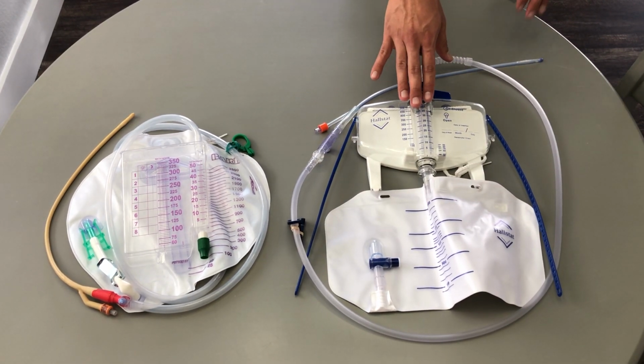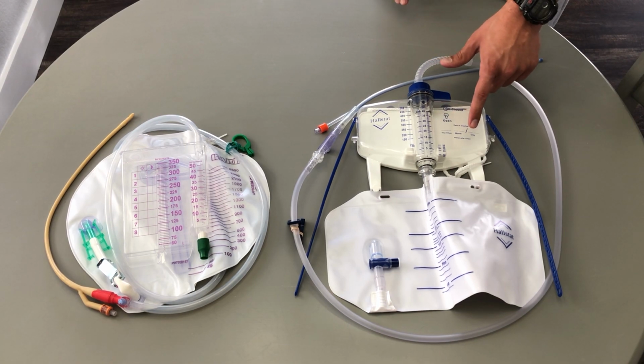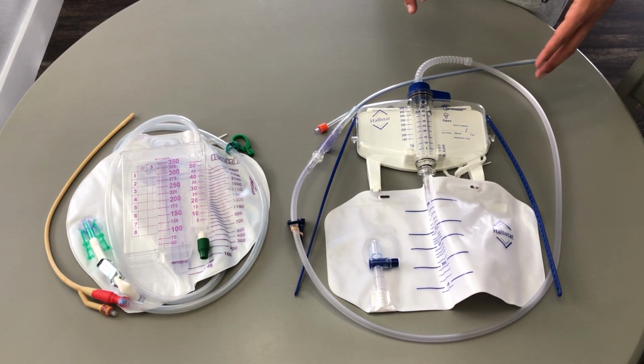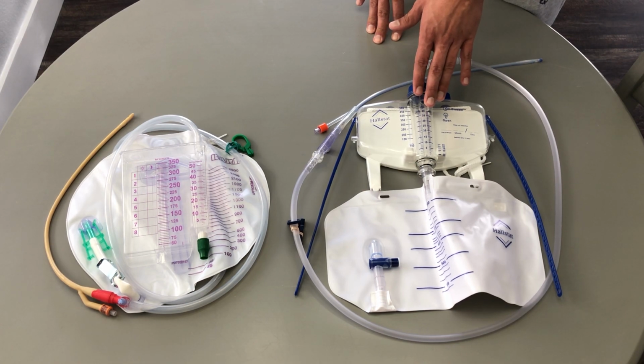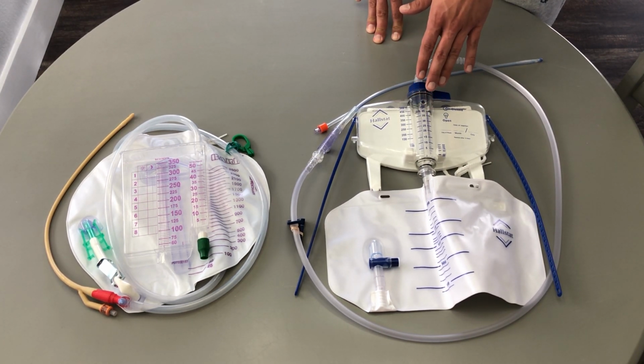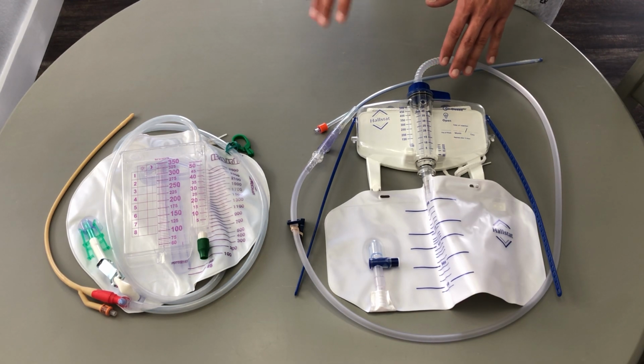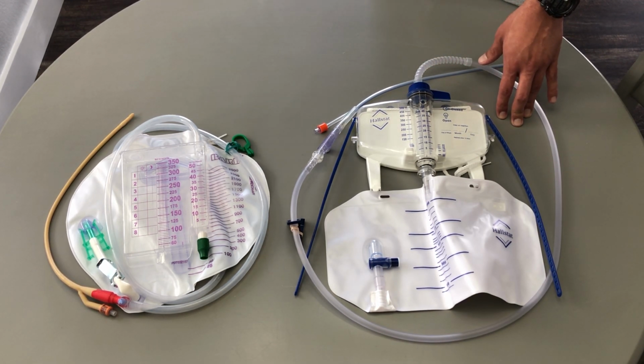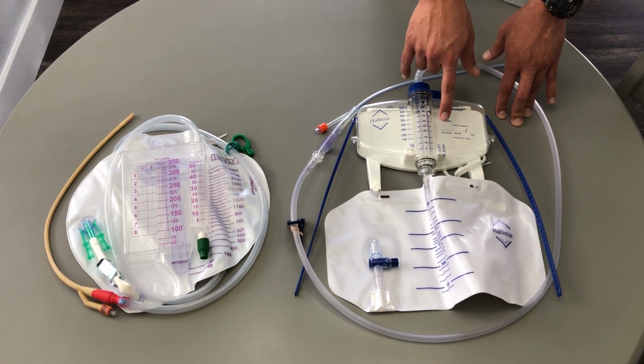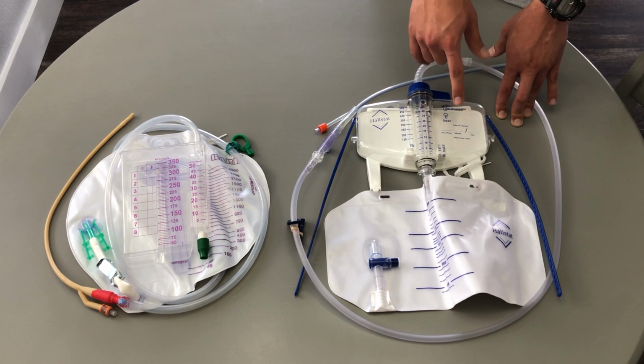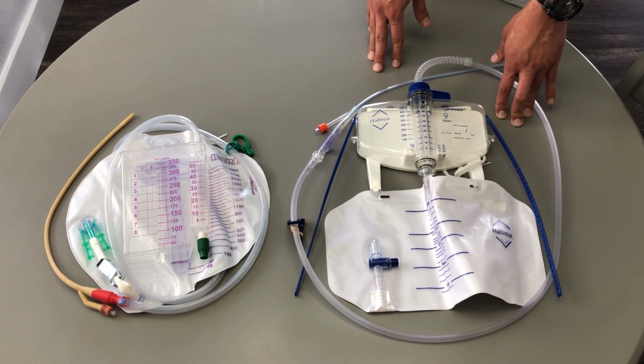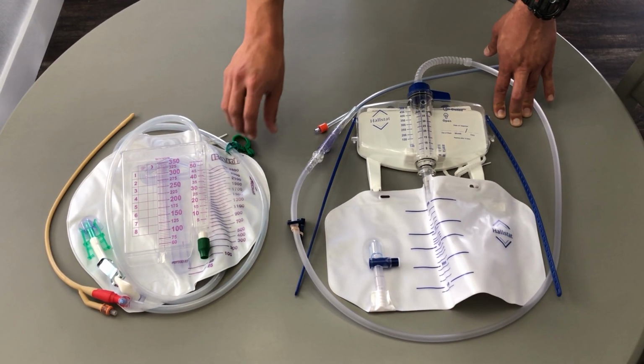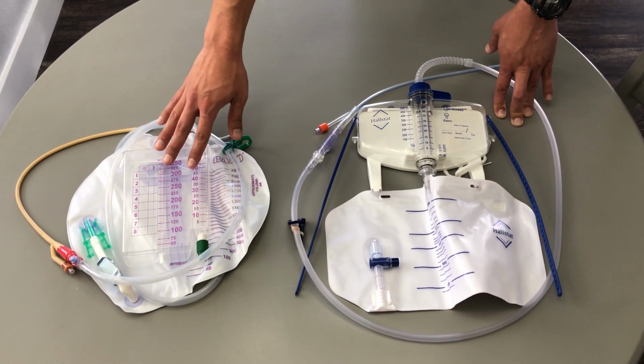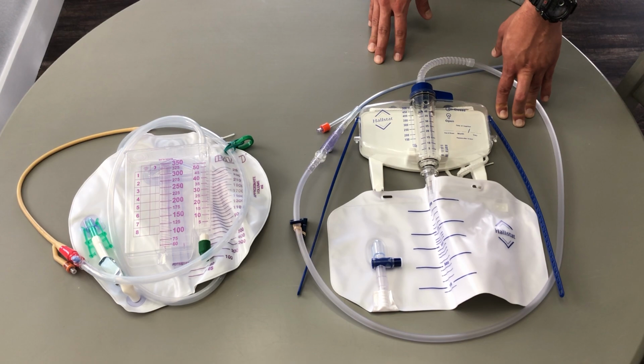Besides that, the Halyard catheter system also has a better dating system, which is right in front of the urine meter. This is significant because indwelling time is very important when it comes to reducing infections. The FDA only allows these systems to be inserted inside of a patient for up to 28 days. Really, anything past 15 days will increase your chance of getting a UTI significantly. But especially if you go past 28 days, then it will greatly increase bacterial growth. So having a proper dating system significantly helps the nurses to remove the catheter at an appropriate time. Whereas a Bard system comes with a sticker which you place in the back and is not visible, and often creates inappropriate usage when it comes to removal of the catheter system.